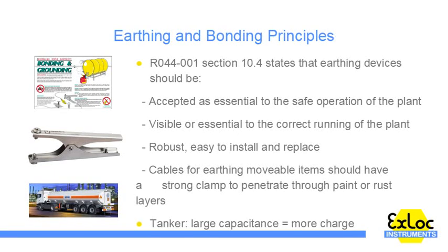An aspect of electrostatic charge accumulation that we have not yet considered is the capacitance of a conductive object. The larger the capacitance of an object, the more charge it is able to store. One of the largest movable items to be seen in industrial hazardous area operations is the road tanker, delivering or taking away product.